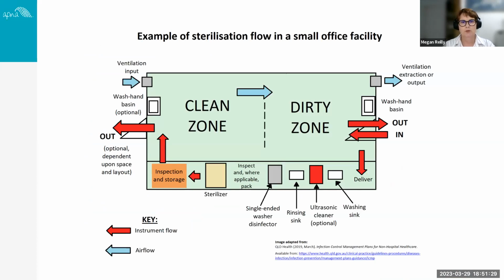So this slide just gives you an example of the reprocessing flow in a small office space practice. We can actually see we've got an in and an out door into the dirty zone, which is actually quite acceptable. Ideally, we would like to have the unidirectional flow going right through from dirty into clean. There is the opportunity to separate this out physically, or a space barrier is acceptable. And we can see we've got that out door, which is currently optional.